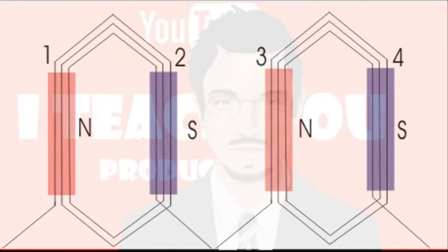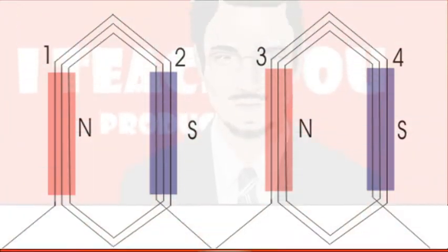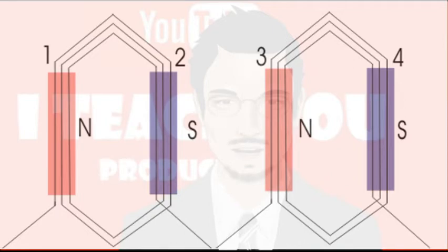Here, number of poles equals number of slots equals number of coil sides. Here, one coil side is inside one slot under one pole and the other coil side inside another slot under the next pole. Clearly the EMF induced in one coil side is added to that of the adjacent coil side. This arrangement of armature winding of an alternator is known as skeleton wave winding.